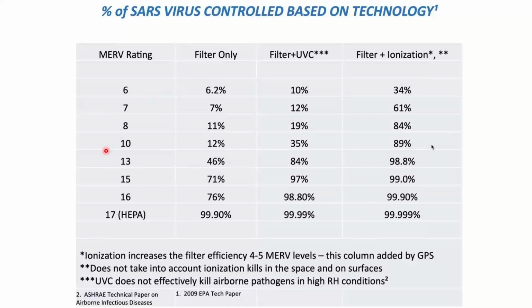What I was saying was, if you take a Merv 13, ASHRAE's bare minimum for a chance at catching COVID, it catches 46% of this surrogate SARS virus. If I combine it with ionization, it gets almost 99%, which is significantly better, obviously. And if I can't put Merv 13 in because of the pressure drop, and I decide Merv 10 is all my current duct system can handle, I can put a Merv 10 in. By itself, it's almost useless, 12%. But with ionization, it's up to 89% capture or kill rate, however you want to look at it. That's what I was kind of illustrating in the last one. So I apologize for not showing the slide as I was saying that.